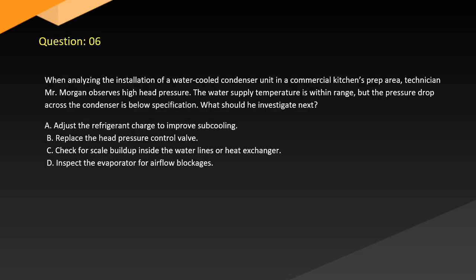Question 6. When analyzing the installation of a water-cooled condenser unit in a commercial kitchen's prep area, technician Mr. Morgan observes high head pressure. The water supply temperature is within range, but the pressure drop across the condenser is below specification. What should he investigate next? A. Adjust the refrigerant charge to improve subcooling. B. Replace the head pressure control valve. C. Check for scale buildup inside the water lines or heat exchanger. D. Inspect the evaporator for airflow blockages.